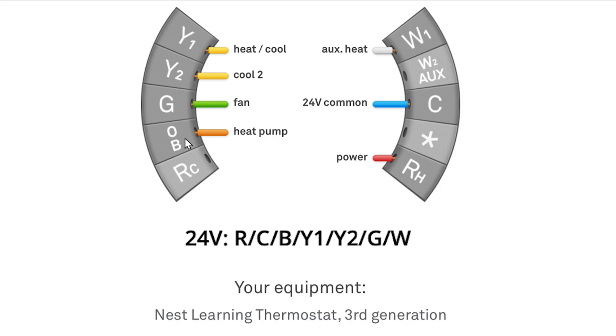The OB wire is important — as you see here, it is set to B. You can select it to O, and Nest likes to say O is the most common, but the fan will run and you're not going to cool. So you want to go with B. W is Auxiliary Heat, C is 24-volt common, and R is power. They've color-coded it really well: R for red, C for cyan/blue, W for white, Y for yellow, G for green, and O for orange — but again, yours should be set to B.